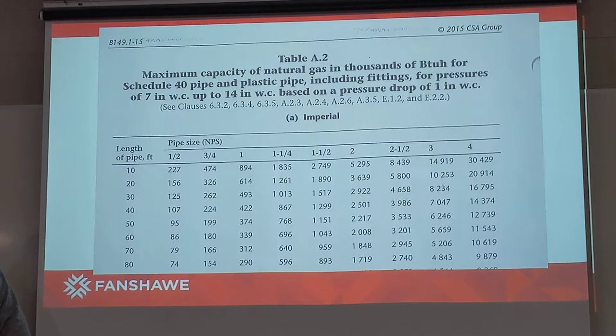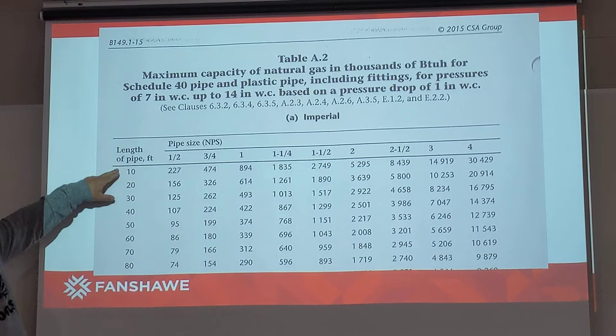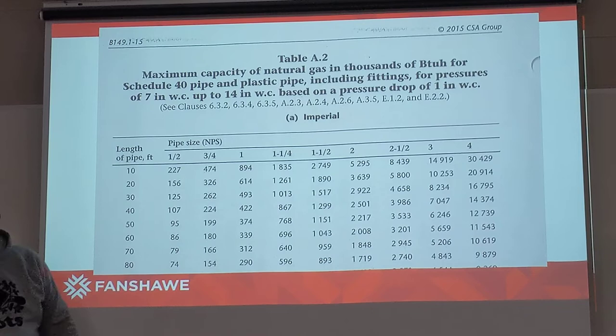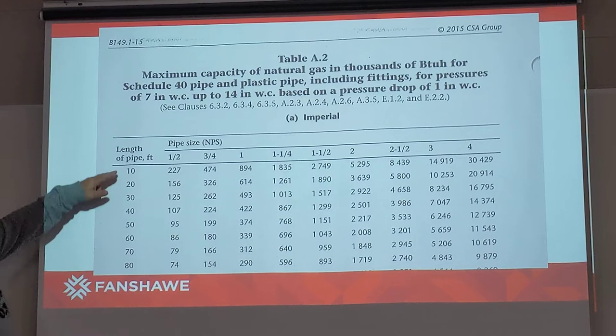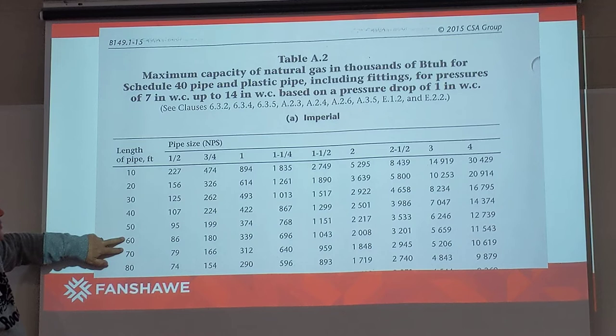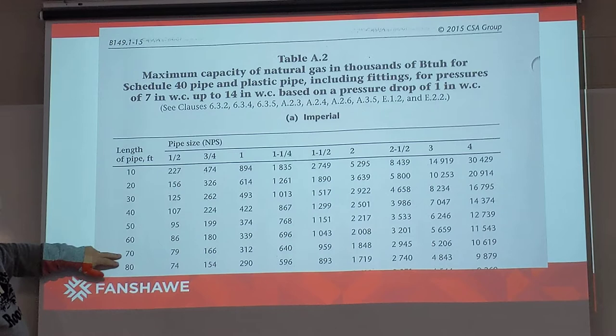The table at this point looks like this — I'm going to shrink it down so we can see the numbers we're after. The actual page number is page 118 in the B149.1-15 code book. Taking a section of Table A2, we can see the length of pipe in the left-hand column starting in 10-foot increments. Our longest measured run is 65 feet, so we're in between 60 and 70 feet. Our worst case scenario is always the longer run, which is going to be 70 feet because we're in between table values.